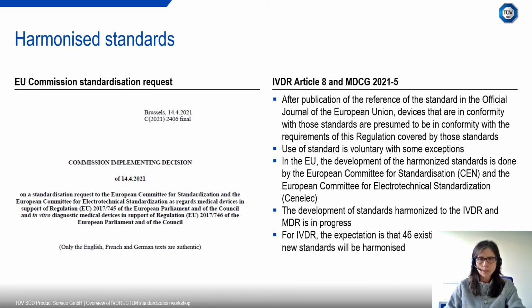I would like to also say a few words on the use of harmonized standards. This is included in the regulation under Article 8, and there is also an MDCG guidance clarifying the use of harmonized standards. What Article 8 says is that if a device is in conformity with a harmonized standard, it is presumed to be in conformity with the corresponding requirements of the regulation. The use of the standard is voluntary. It's quite widely used, but is still voluntary.